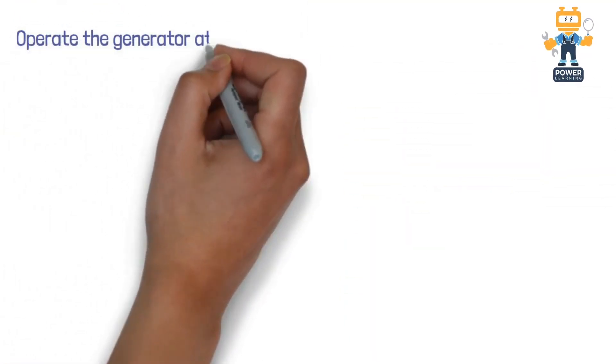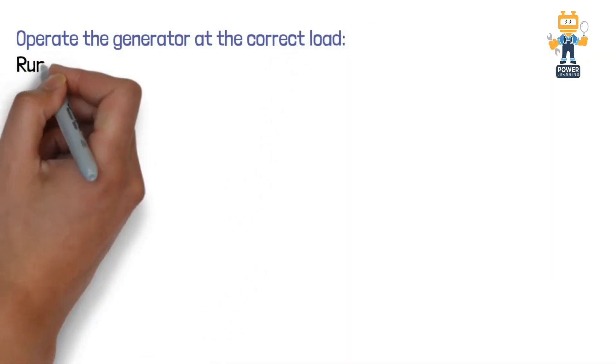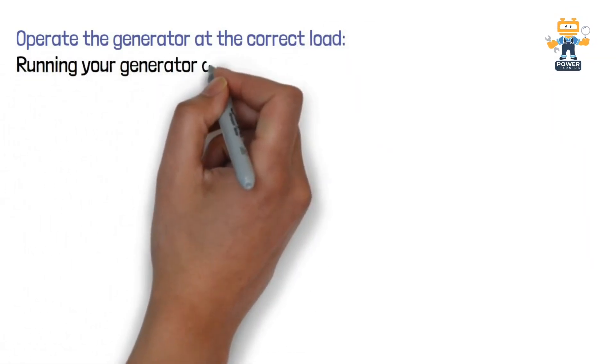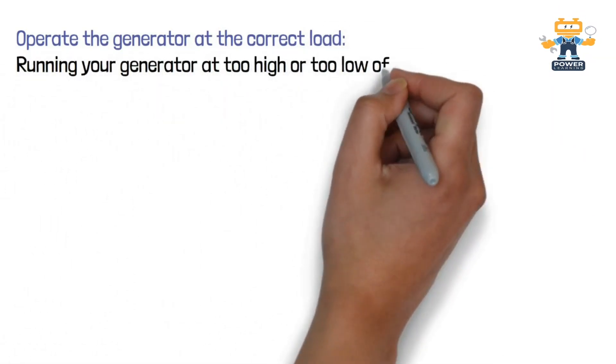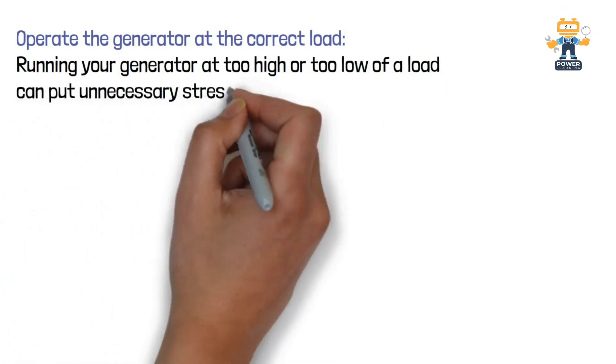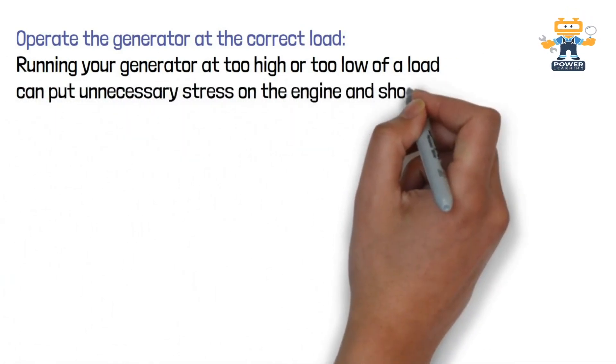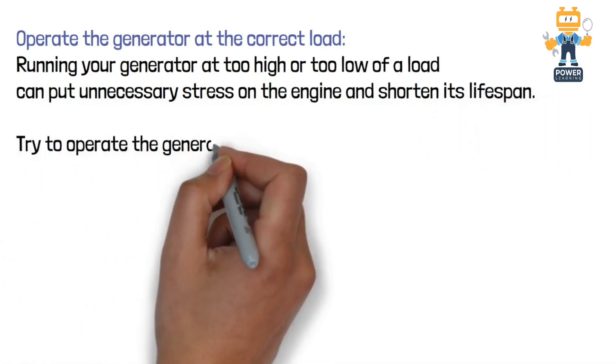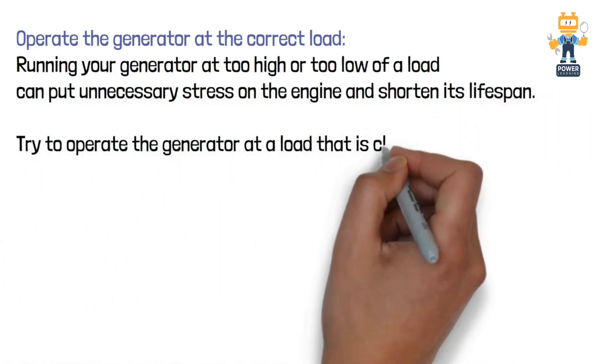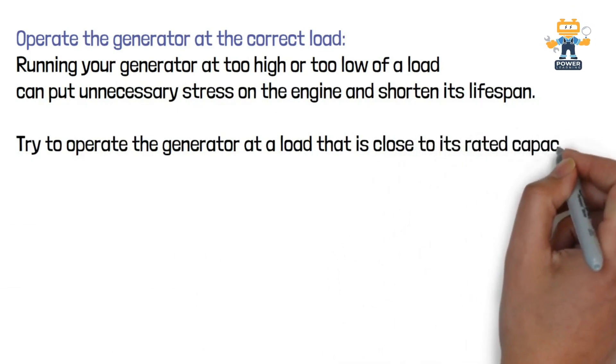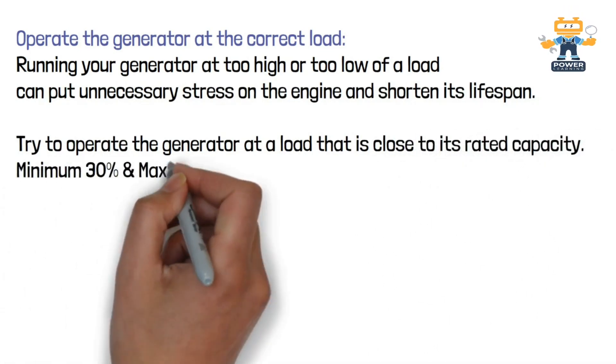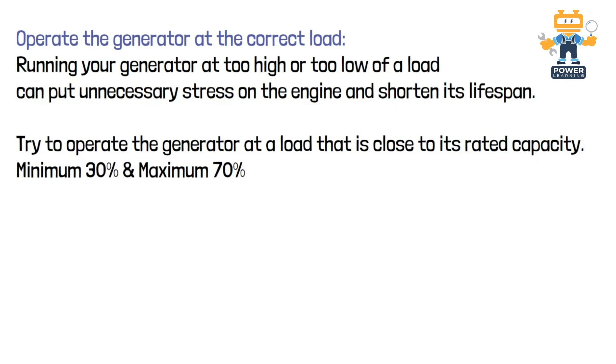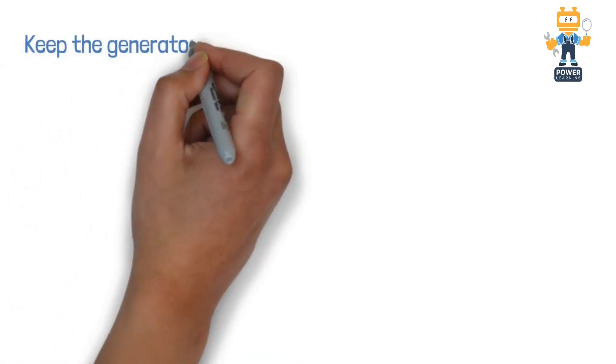The next point is: operate the generator at the correct load. If you run your generator at too high or too low a load, you can put unnecessary stress on the engine and shorten its lifespan. Always balance the load and operate the generator at its rated power. Try to operate the generator at a load that is close to its rated capacity—minimum 30% and maximum 70%. This is the ideal load for diesel generator operation.